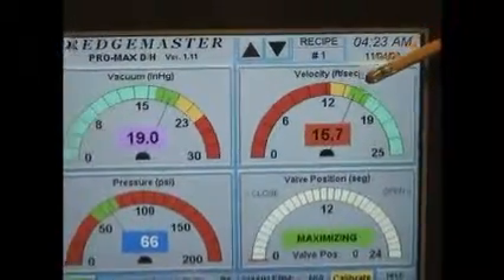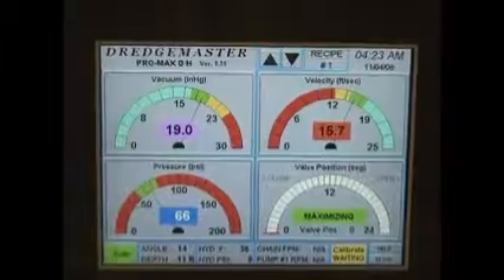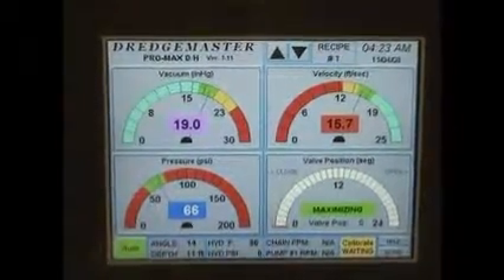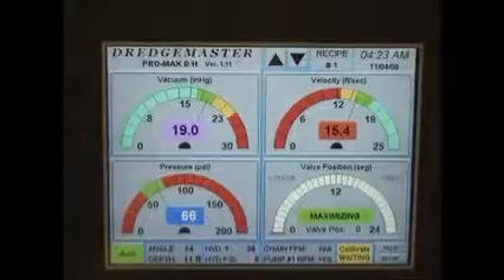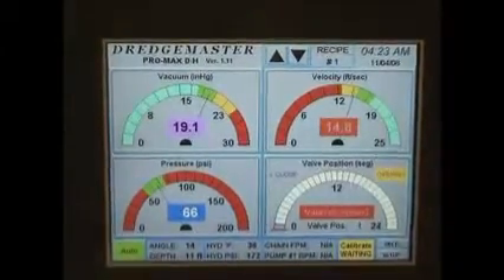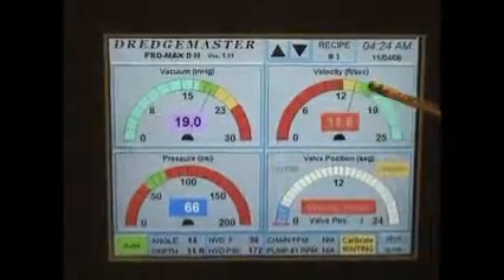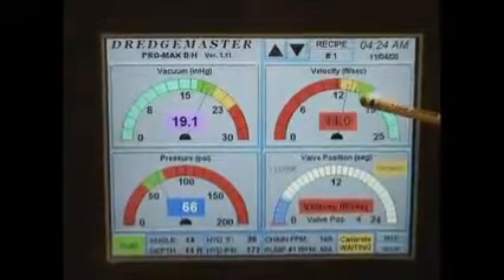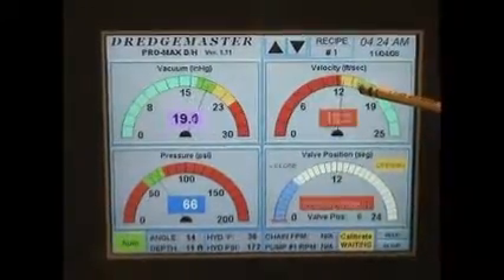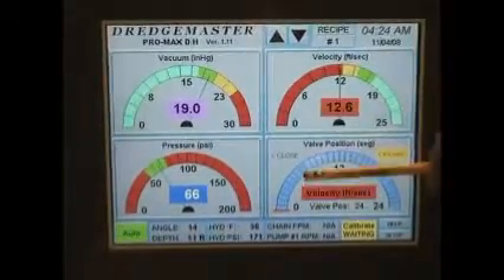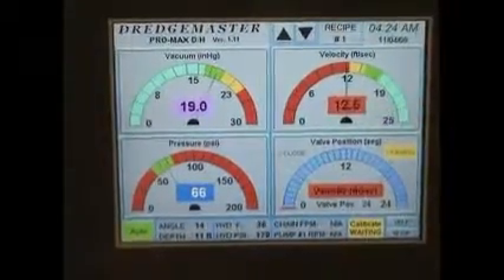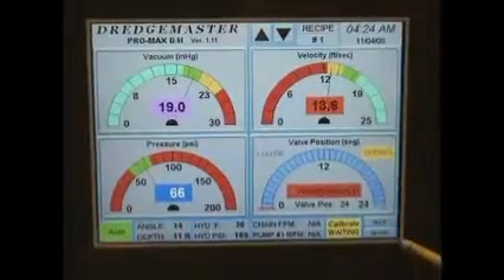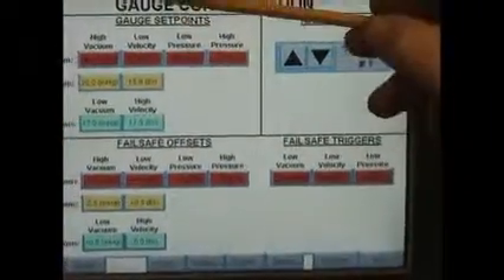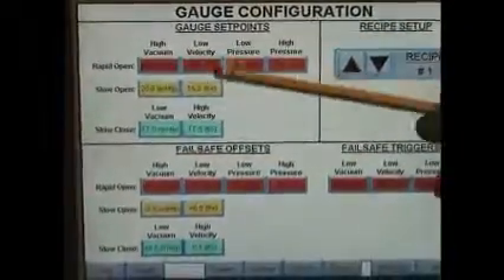We're going to go to the main screen, and now you can see our parameters have changed here. So now we have to get down to 15 feet per second or less for the valve to start opening. And once we get to 13 feet per second, our valve will rapidly open, as you can see. So we just changed the set points of our color zones by simply touching the setup button and going to the gauge set point, which is right here for the velocity.